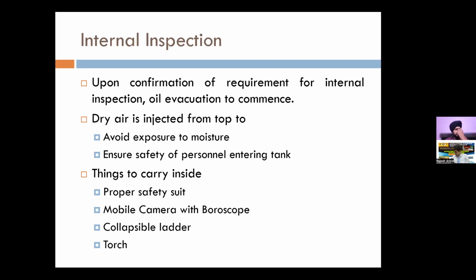Then recently, based on our experiences, because our transformers are now getting smaller due to more optimization of design, there are many places inside the transformer, particularly around the winding, where a person cannot actually go and see what has happened. So a mobile camera with a borescope is helpful in such conditions. At PowerGrid also, we have now procured these special borescopes. Whenever there is some hard to reach place, we simply connect it to the mobile phone. These are 1 to 2 meter long optical fibers, and with that we can also see what has happened at places which are more challenging to get a visual inspection.